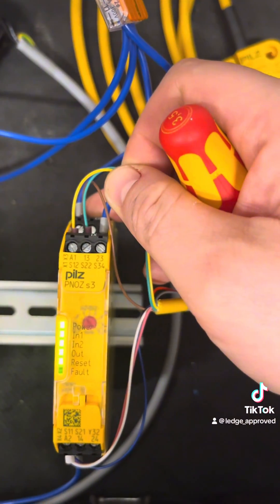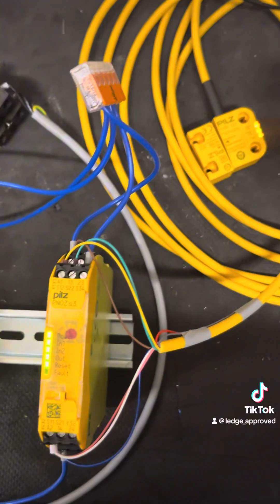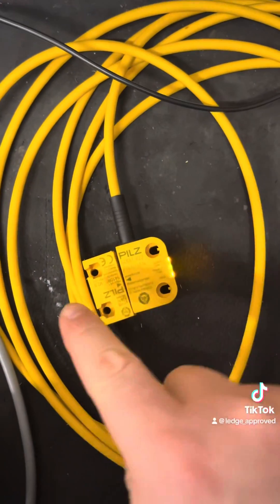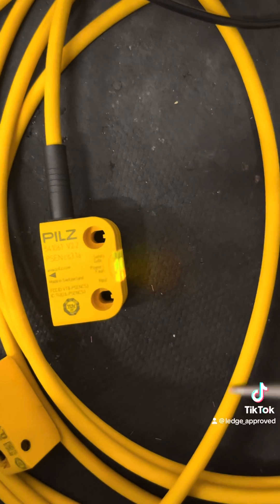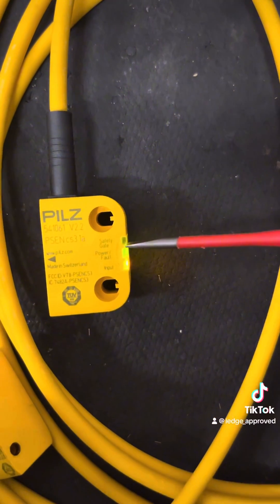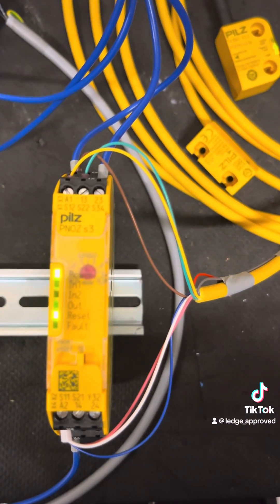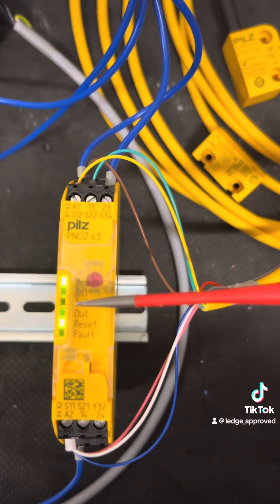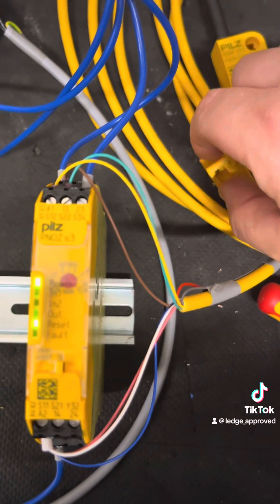And if you want, I could go into a bit more. But I still have channel one and two coming back, and they will break. So if I was to take one of them out on the actual relay, it would fault. So what I'm showing you now is if I take that mag away, I am showing open gate. And I have lost channel one and two.